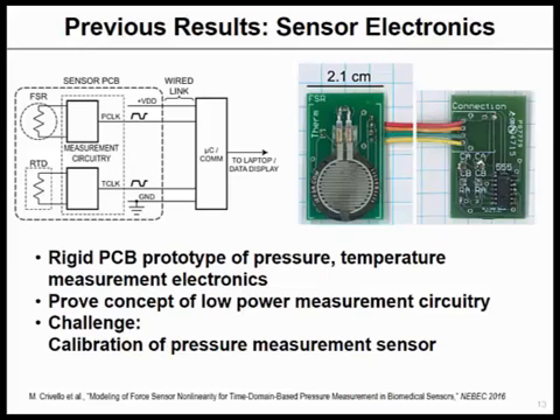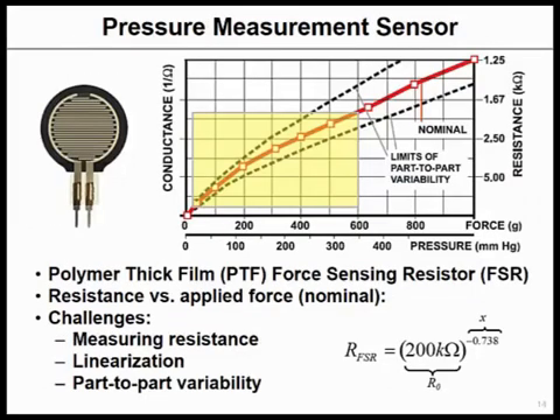The challenge here is calibrating the pressure measurement sensor. Shown here is the characteristic of conductance on this axis versus force on this axis. When we normalize it to pressure in millimeters of mercury, it's this yellow area for the range of pressures that we'll be measuring in this application. So the red here is the nominal characteristic.